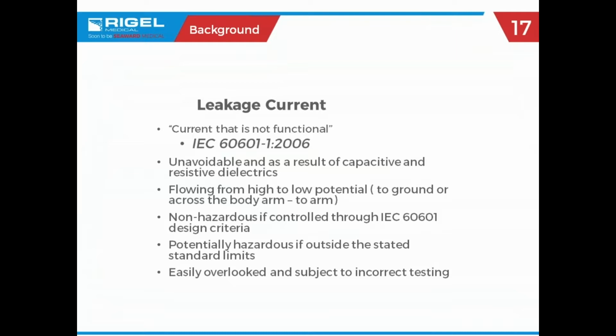So leakage current. Whoever came up with that first bullet point, brilliant. Leakage current. Current that is not functional. Not doing any real work, right? There's always going to be some level of leakage current. We measure this in microamps. It's unavoidable because of capacitance and inductance, if something's around a coil of wire and it's metallic. If that coil of wire has current flowing through it, you're going to induce current in the metal object. So it happens, it's always there.